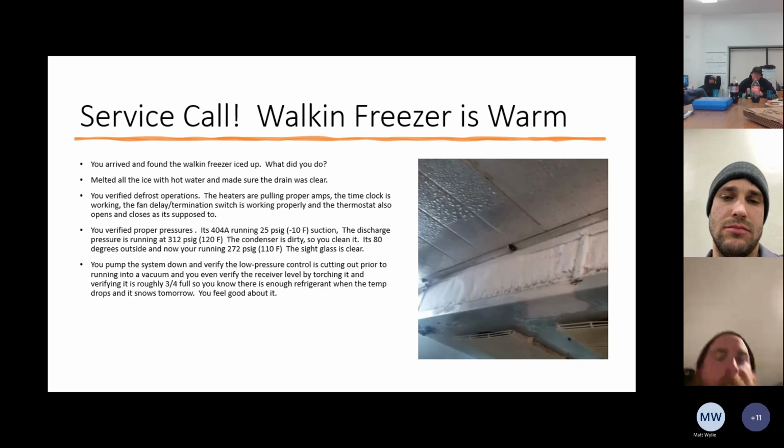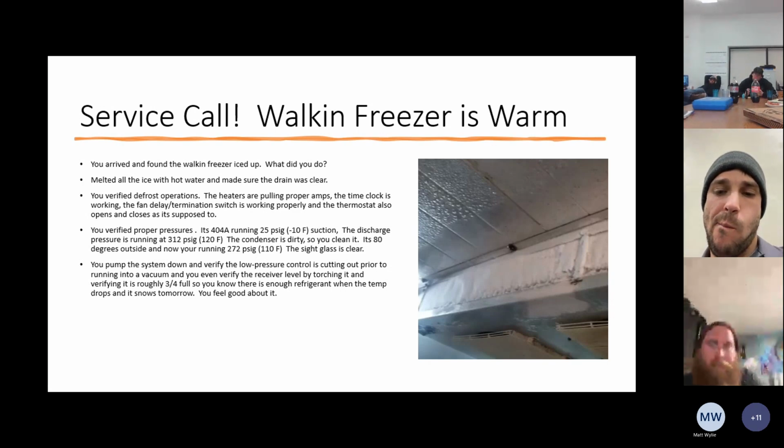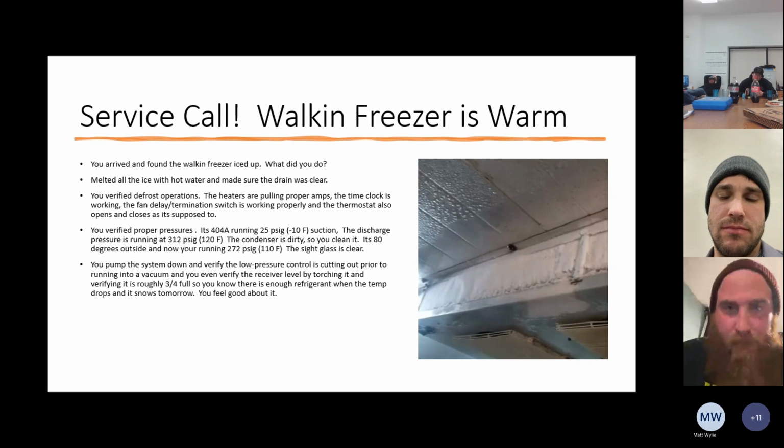What are some things that you'll check before adjusting the expansion valve if you have high superheat? Airflow, we got. High superheat. One of them was something that was held up in front of the camera for everyone to see. Oh, yeah, restrictions, I guess. But what specifically? TXV, filter, screen. Yep. Okay.